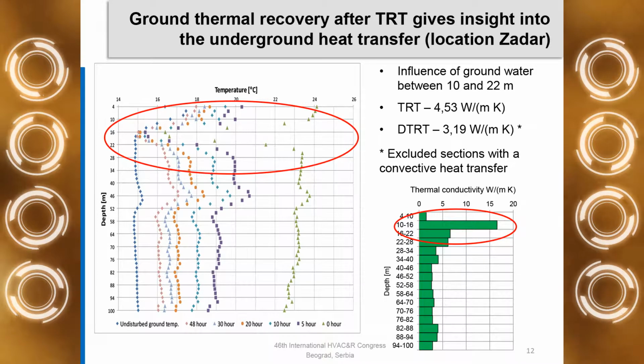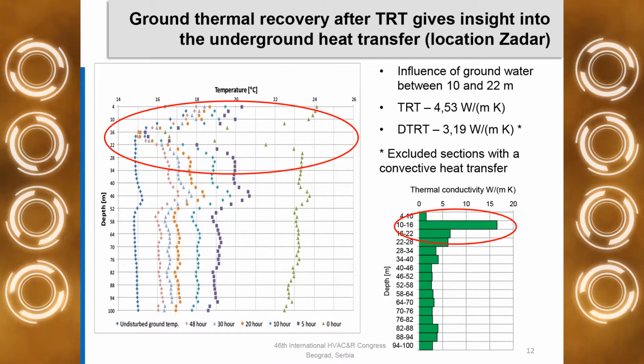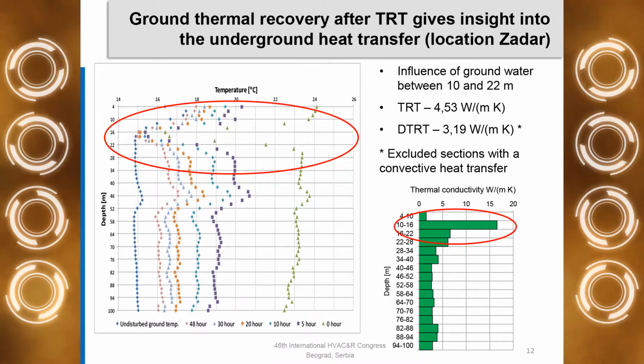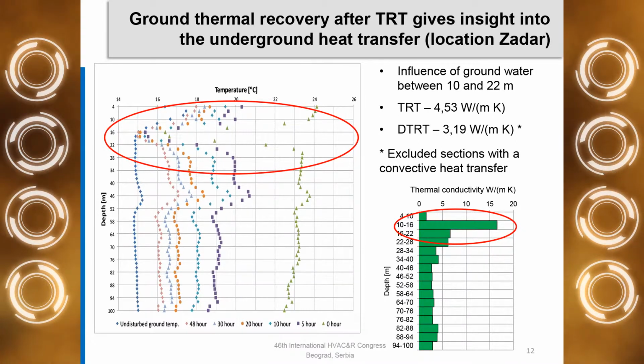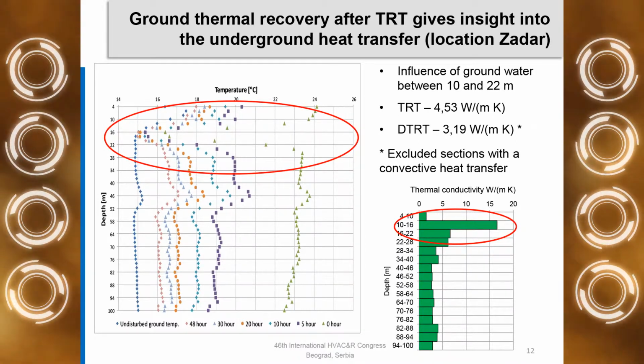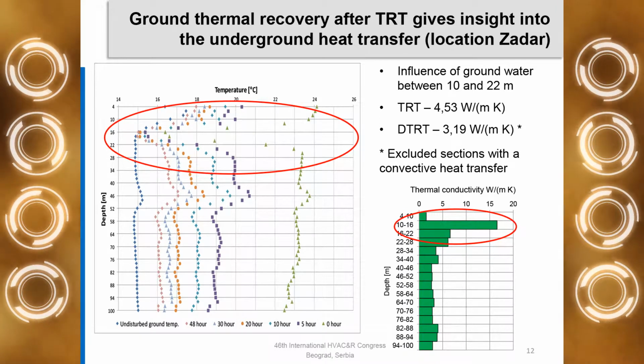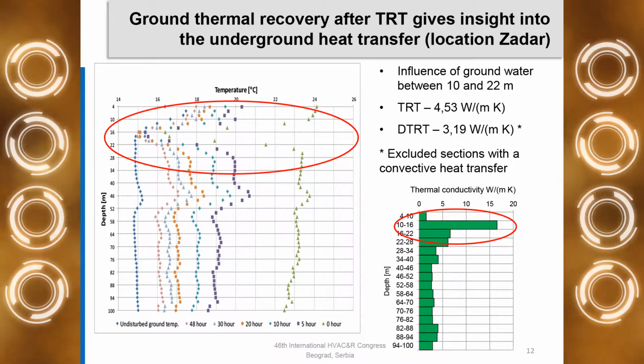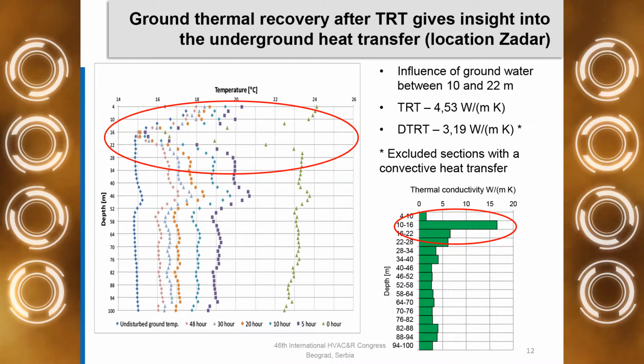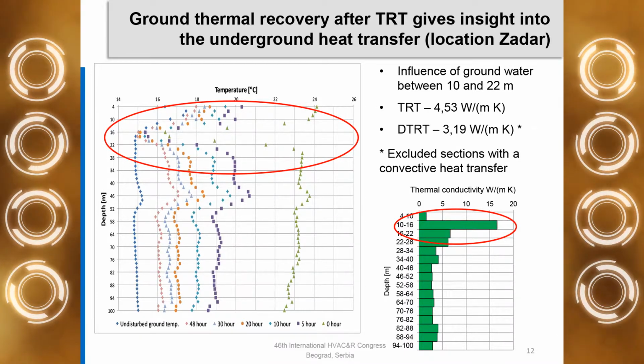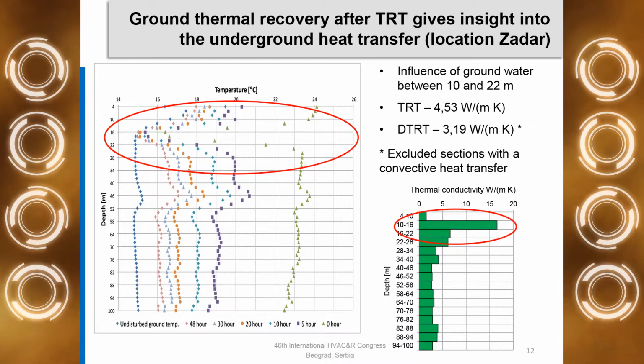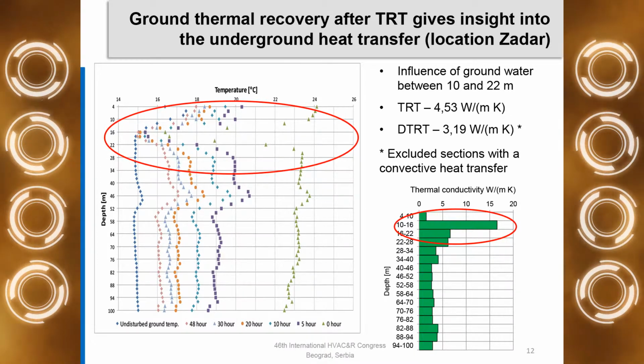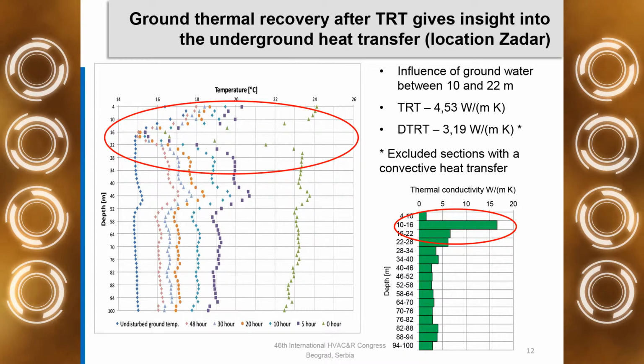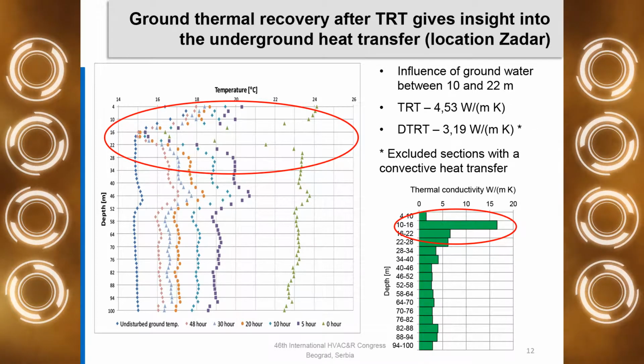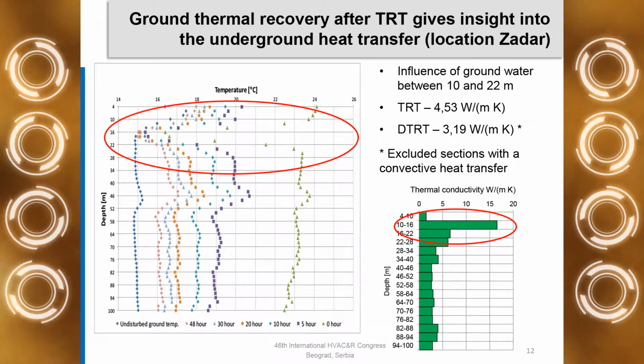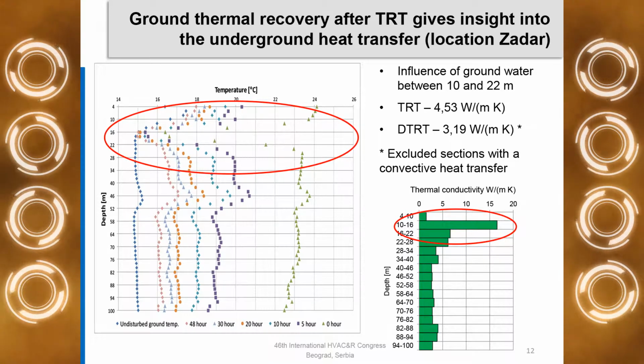If we plot the obtained thermal conductivity, we see that there is an unphysically high value of thermal conductivity found there, indicating that there is actually increased groundwater flow that results in convective heat transfer that is not covered by a line source model used to obtain this data. If we compare the TRT data and distributed thermal response test data when excluding sections with convective heat transfer, those are those 3 or 4 layers, the difference is around 1.3 watts per meter Kelvin.